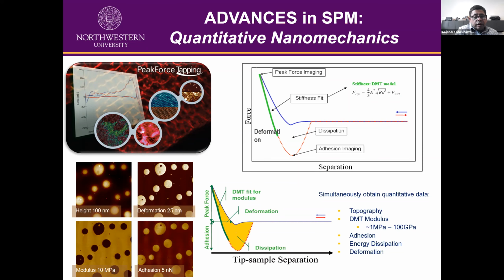And the most important part here is the probe selection. You can choose an appropriate probe of a different stiffness, or spring constant, and measure those mechanical properties, energy dissipation, and deformation. And then you can see in the images here, at the bottom left, you can also get a typical topography image, deformation image, modulus image, adhesion image. So it's a very popular technique, and we have this technique on all of our systems.